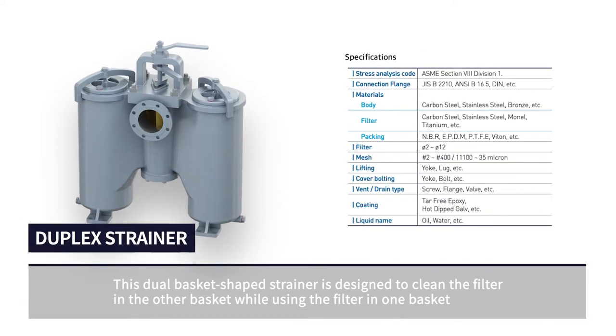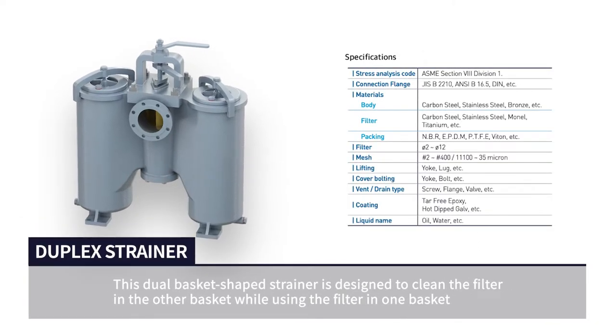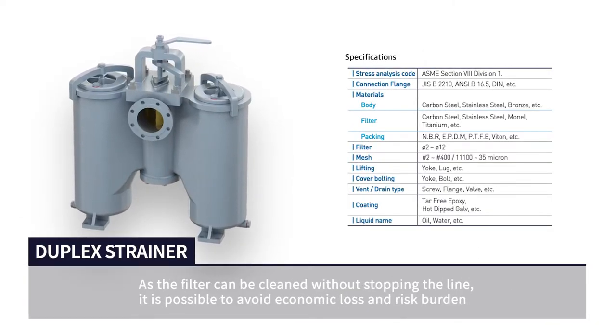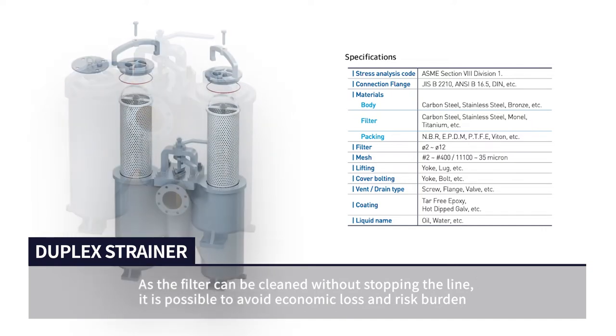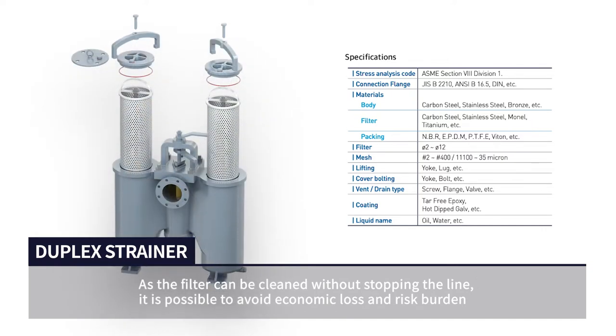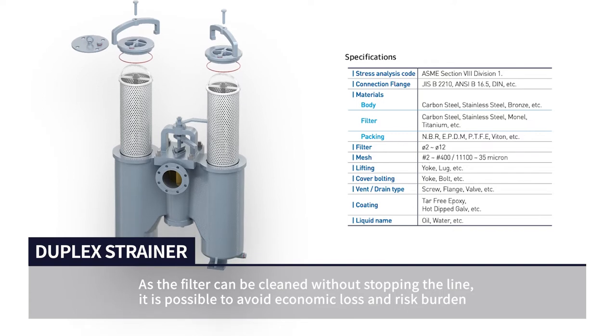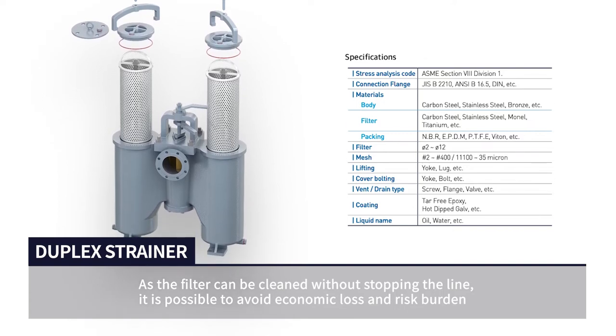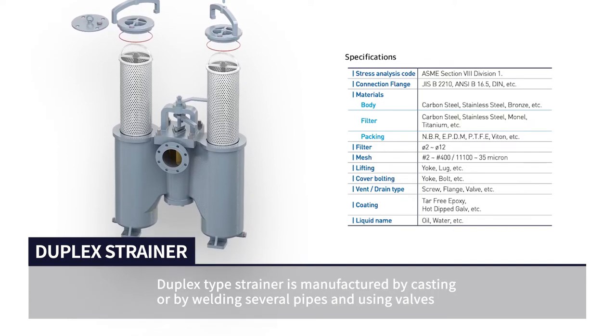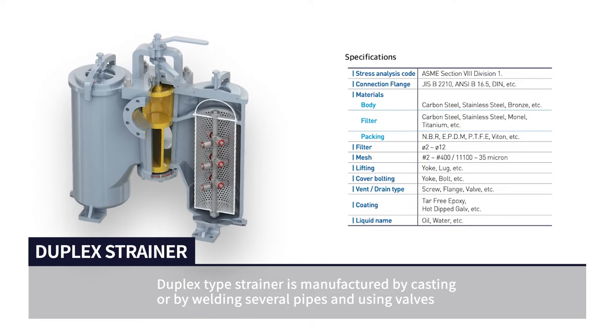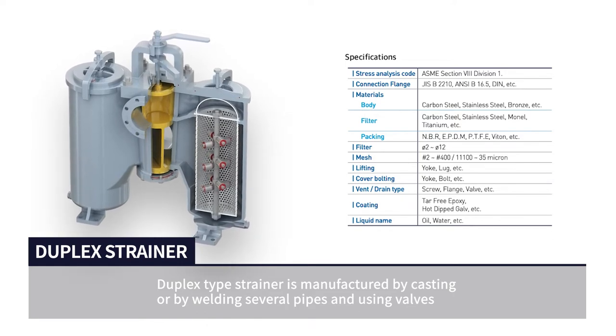This dual basket shaped strainer is designed to clean the filter in one basket while using the filter in the other. As the filter can be cleaned without stopping the line, it is possible to avoid economic loss and risk burden. Duplex type strainer is manufactured by casting or by welding several pipes and using valves.